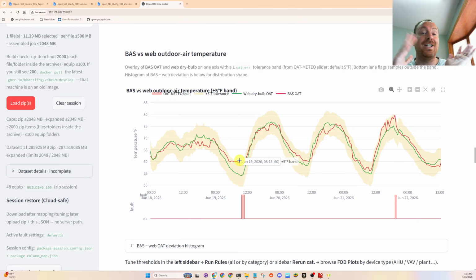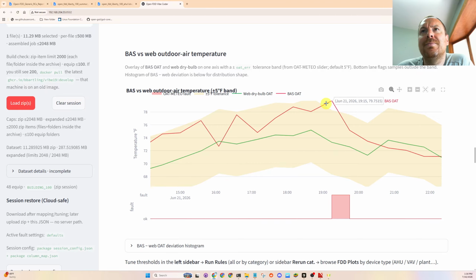Rarely are they calibrated; they're replaced. And then if they're calibrated, there's usually kind of a wonky offset that they do in the programming tool, where they'll just plus 2 degrees or minus 2 degrees or whatever the offset is. So it's never perfect. Calibrating sensors in building automation is kind of a joke a little bit, because there's only a fixed offset that the technician can do with a product line that they buy from the manufacturer. And as you can see, these are changing constantly. It's never fixed. Even here, the sun might be shining on the sensor. These might be clouds. Who knows?